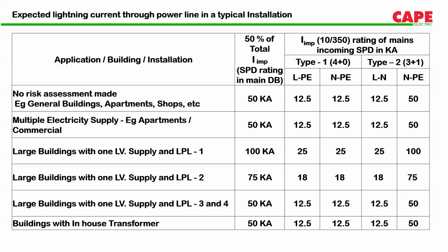Based on that, if the building comes in level 1 and level 2, the minimum impulse current rating required in an SPD to be called a class 1 SPD is 25 kiloampere. Whereas in level 3 and level 4, the minimum lightning current required is 12.5 kiloampere. Why I have raised this point is because it is a little unfortunate that our Indian clients are confused about what is class 1 SPD, what is class 1 plus 2 SPD and what is class 2 SPD.